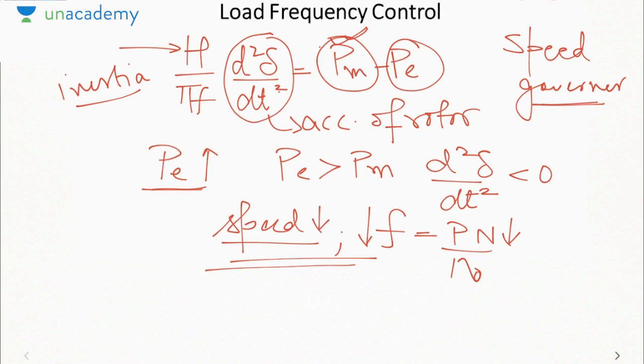But the thing is, speed governor also has certain limitations. It cannot keep on increasing the mechanical input as the electrical output increases. After a certain time, it will reach its limit and then the frequency will start decaying rapidly. So what to do in that case is, we have to shed some load or we have to reduce the electrical power. That means I have to support this electrical power demand with the help of other generators. That is, we have to control the load power.